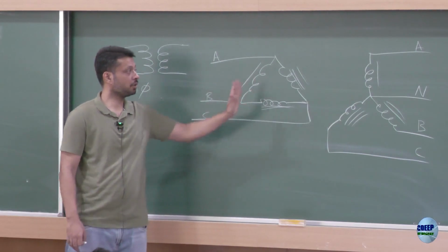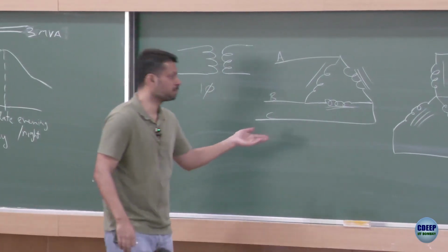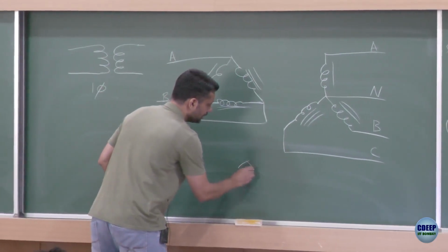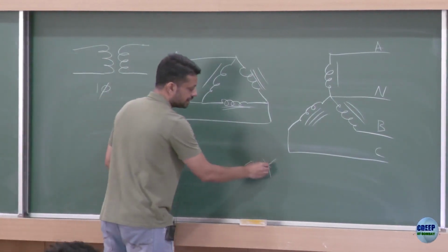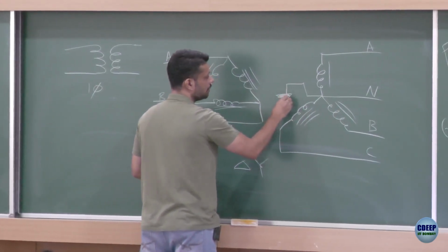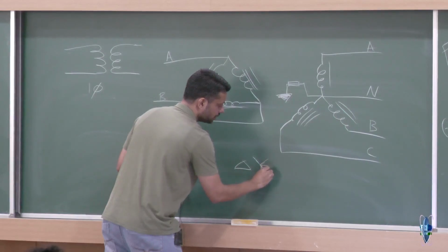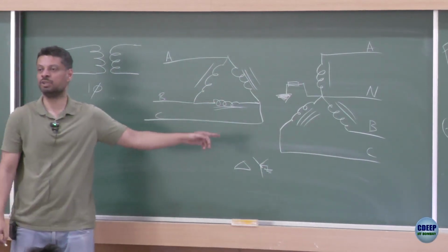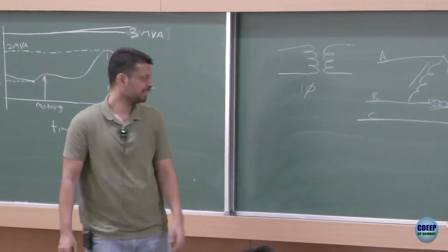In a 3 phase transformer you can have different arrangements. What is this particular arrangement called? Delta star. So, this is a delta star transformer. The star point is also earthed, either directly or through a resistance or an impedance, and therefore this is how it is shown in the symbol. That means it's delta star with neutral point earth. Okay, this is the symbol.